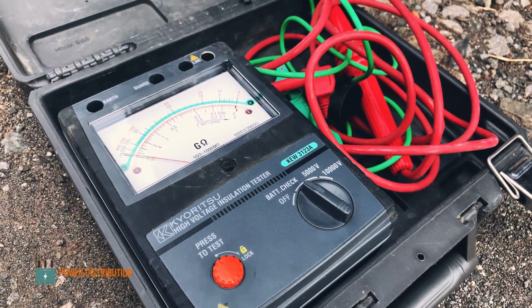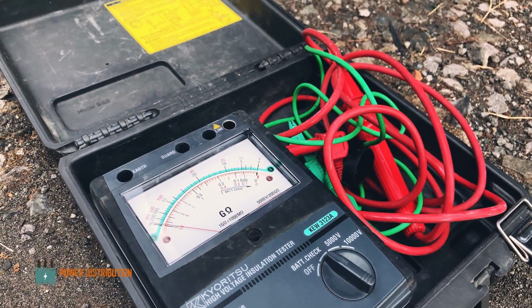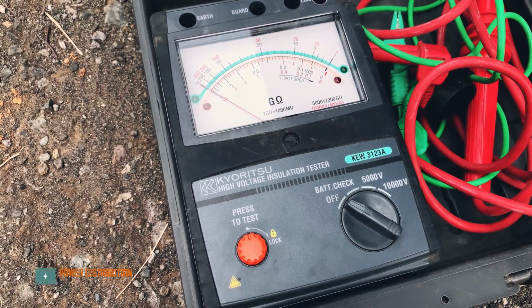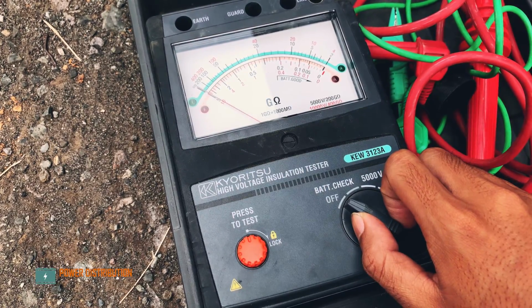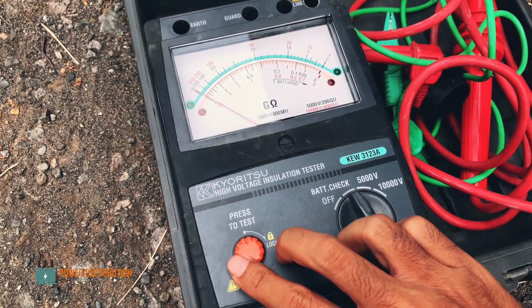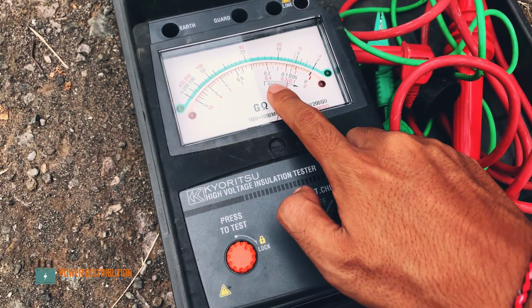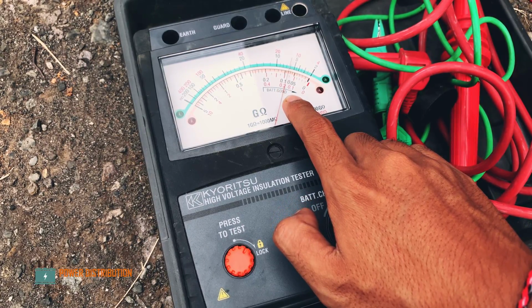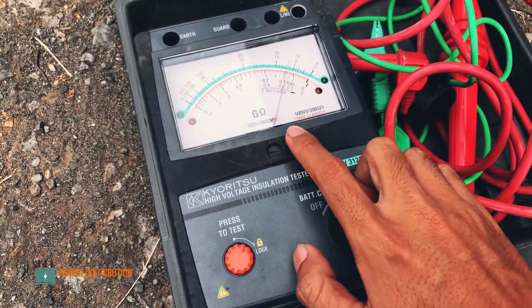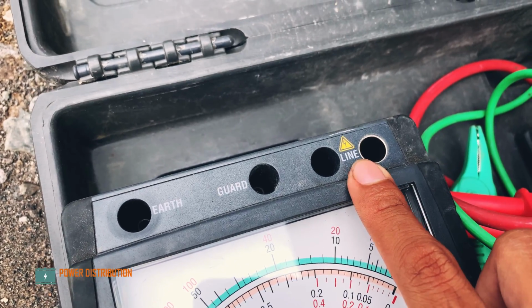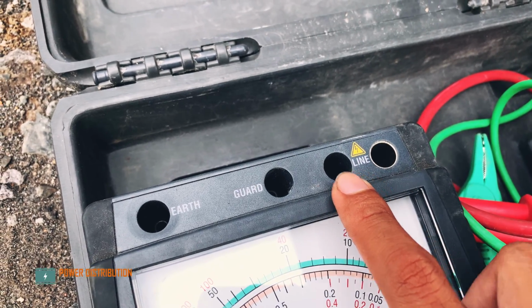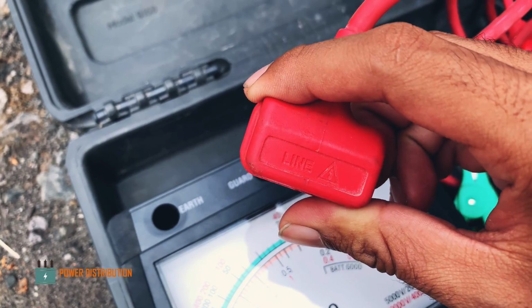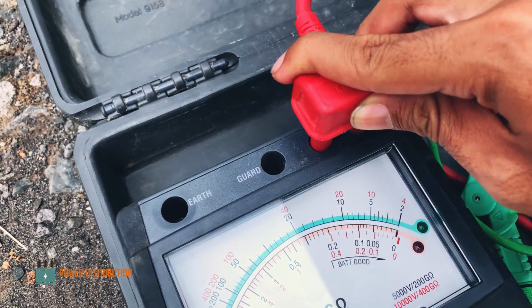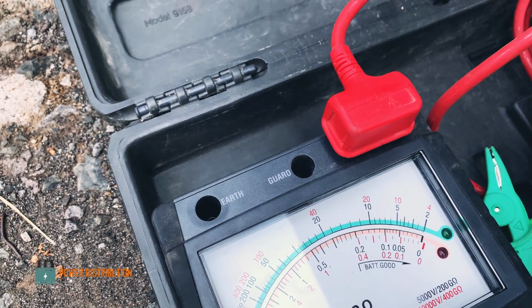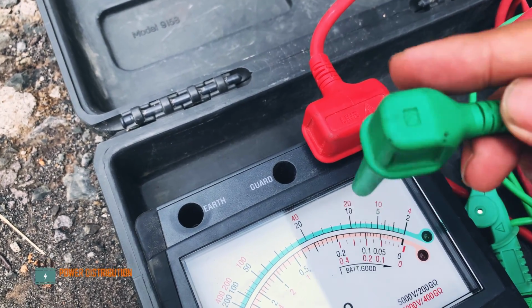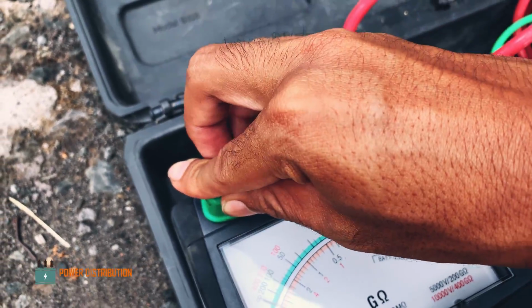Before we use this instrument, it is very important to check the battery condition. Move the selector into the battery check position and then press to start and see whether the needle is still pointing at the good battery indicator. Battery is good. This is the line terminal, the guard, and the earth terminal. Then we put this line probe into the appropriate terminal, and then the earth probe into the earth terminal.